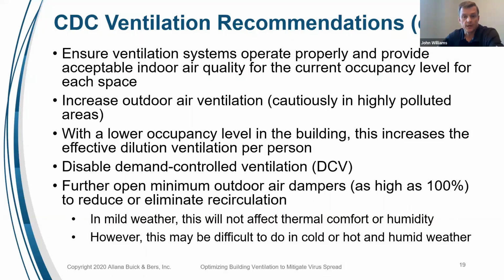Demand controlled ventilation is something that we find in a lot of our buildings, newer buildings or buildings that have been upgraded, where we typically use CO2 monitoring to reduce the amount of outside air during periods of low occupancy. So when we have low occupancy in the building, we're closing off that outside air to save energy. However, because of the coronavirus, we want to override that right now, and we want to try to ventilate more. We want to bring in more outside air. This will likely result in some higher energy costs, but the purpose of this is to increase the ventilation in the short term in lieu of higher energy costs.